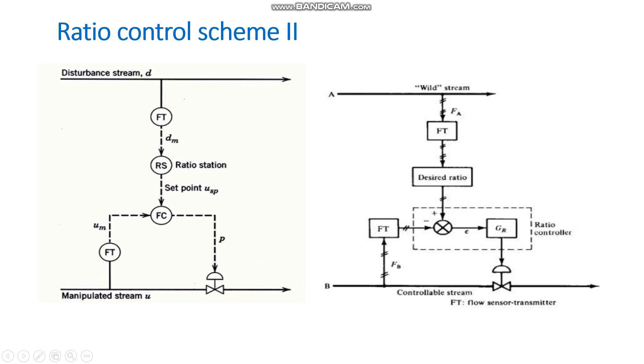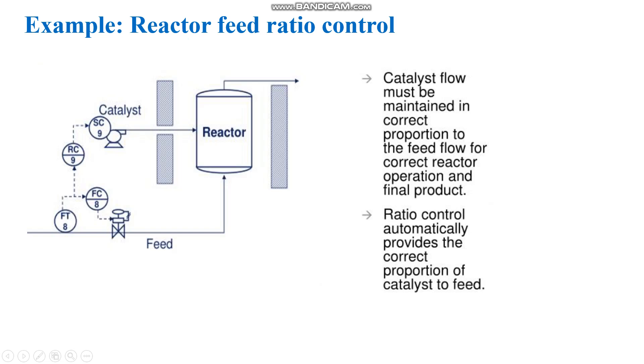The manipulated stream — the controllable stream — is measured by another flow meter. These two measured values are compared in the flow controller, and the output of the flow controller goes to the control valve, which increases or decreases the flow accordingly. This is the controllable stream and the wild stream in scheme two. This is ratio control scheme two.